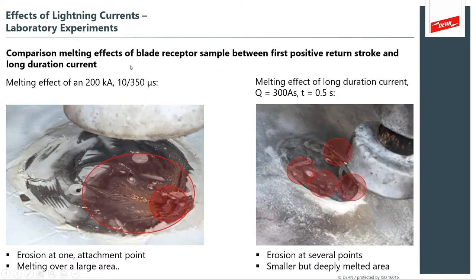Here are images comparing the melting of the blade receptor from first strokes versus long-duration events. The primary stroke — what we call the 10 by 350, 200 KA event — creates erosion and melting. But from the low-amplitude event, the tremendous charge delivered over that comparatively long time interval produces smaller but deeply melted areas and erosion pitting throughout the test unit.